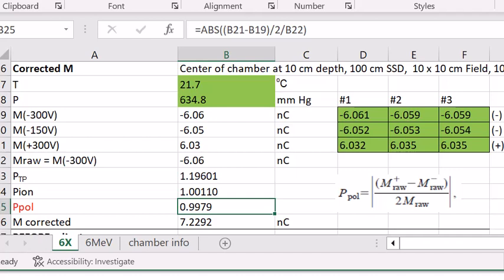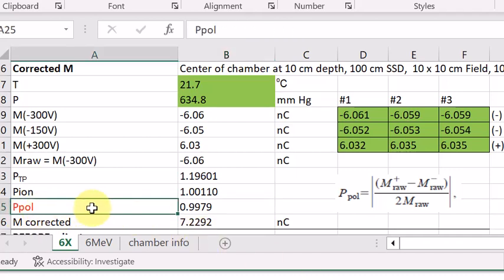And for this particular example, 0.9979 or around 99.8%, this means our chamber biased at negative 300 and positive 300 will make about 0.2% difference in reading. And this is corrected by this P-polarity factor.